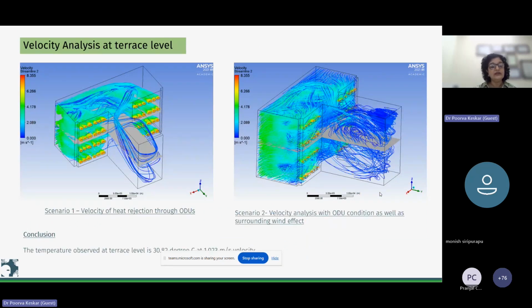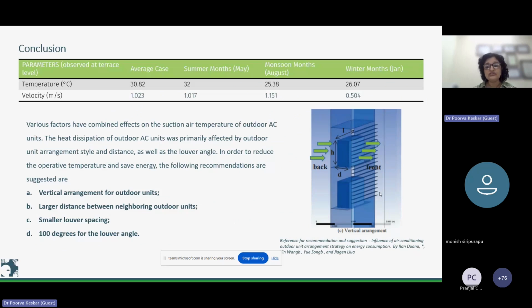So we realized we needed changes to the way the outdoor units were placed. We suggested some vertical arrangements for the outdoor units, and thought of increasing the distance between them. We also suggested smaller louver spacing, and the angle of the louver spacing was chosen so people wouldn't get direct draft coming out of these ODUs.